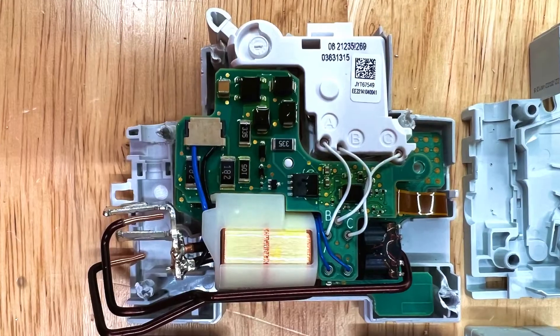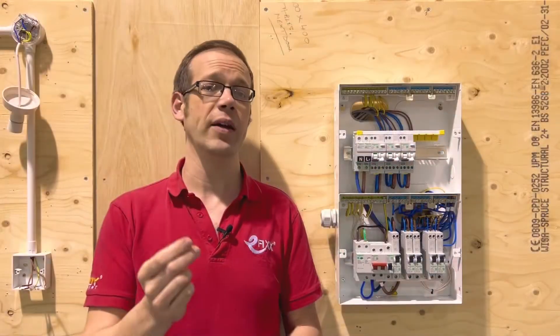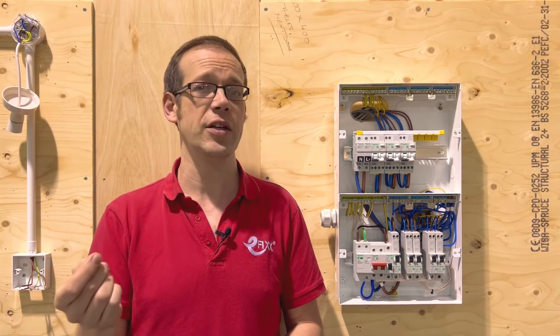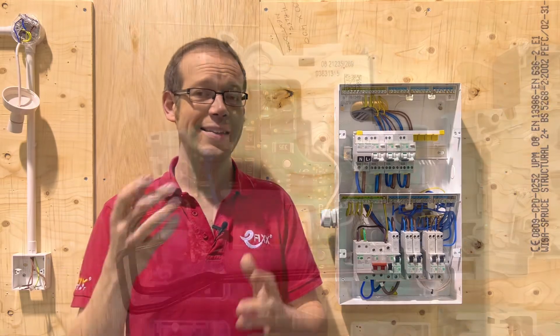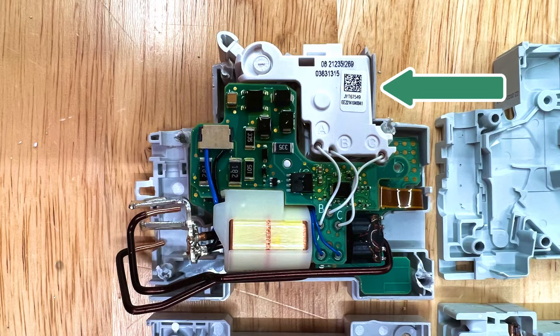Inside the device there is a circuit board that is loaded with software that monitors how the shape of the current waveform is behaving. Then when it sees a distorted waveform that matches the known signature of an arc being formed it sends a signal to the mechanical tripping system inside the device to disconnect the circuit.